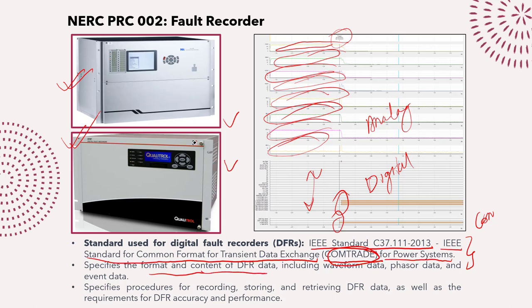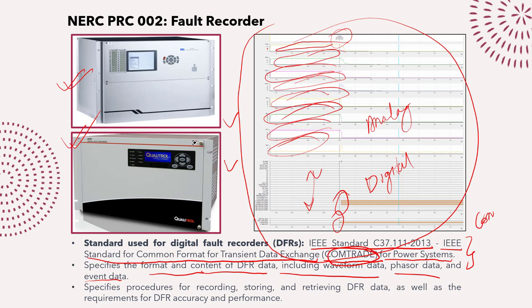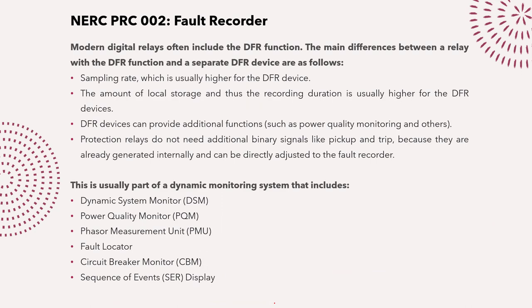The standard specifies the formatted content of DFR data, including waveform data, phasor data, and event data. It defines the triggering location, how status is recorded, how waveforms are recorded, the nominal system frequency, and the number of data samples — which enables analysis tools to perform conversion algorithms and produce the waveforms we observe. It also specifies procedures for recording, storing, and retrieving DFR data, as well as accuracy and performance requirements.